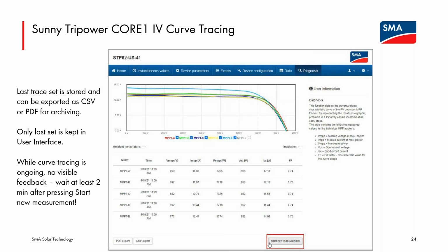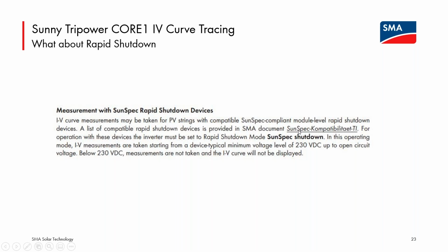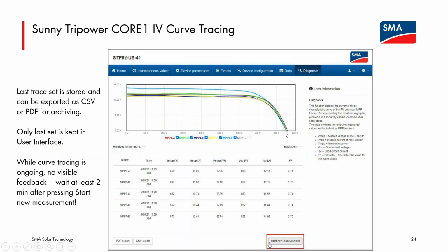So if that transmitter board is turned on, when you click Start New Measurement, the curves will go from VOC to about 230 volts DC. So this part of the curve will not be present, because you'd have misleading data down in the low voltage side. So this IV curve tracing works with or without the SunSpec receivers at the array and does not require any disconnection of the devices from the modules to perform the IV curve tracing. So yet another good benefit, I think, of this feature.